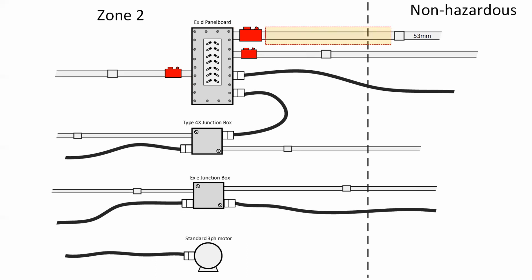Now, what about the conduits which leave the location? The conduits that leave the location would be covered under 18-154, subrule 2. And where they leave this location, they note that there must not be any couplings or fittings or tees or anything like that. But most specifically of interest is no couplings. For the first conduit, it looks totally fine. There is nothing in between the seal and the boundary, and that means we do not need a second seal in the conduit. If we look at this one down below, this one has a coupling right smack in the middle, and that is not permitted as per the rule.